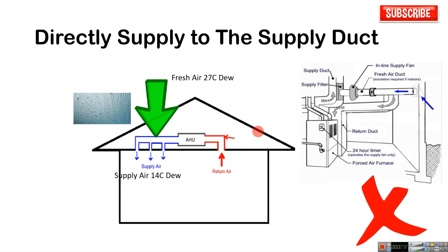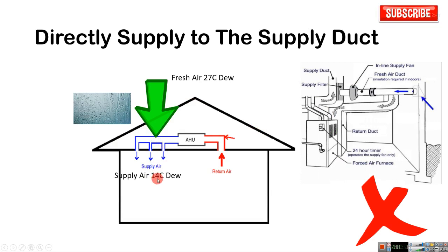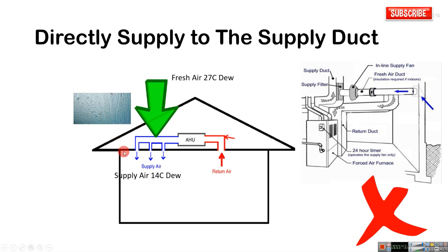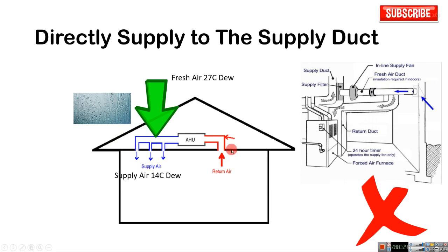Another wrong practice is to directly supply fresh air into the supply duct. The supply duct dew point temperature is very low — it is 14°C. So if we supply fresh air with a dew point of 27°C into the supply duct, there will definitely be condensation, and you can see water droplets coming from the diffusers.